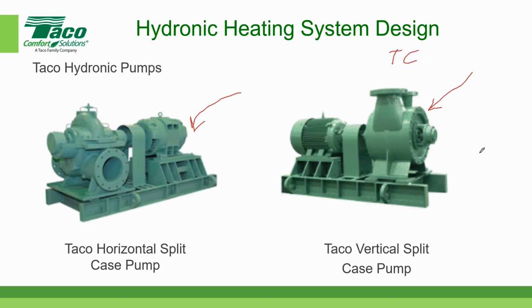And this is called a vertical split case pump. So let's go back to the horizontal split case. The actual casing of the pump, I kind of draw a line here. It's not going to be the best line, but it's split along this horizontal plane right there. And so to dismantle the pump, you unbolt these bolts. You can barely see them in this photograph, but they're there at the top, and you lift off the top half of the pump. And that allows you to service the impeller, the bearings, the shaft, and so on.